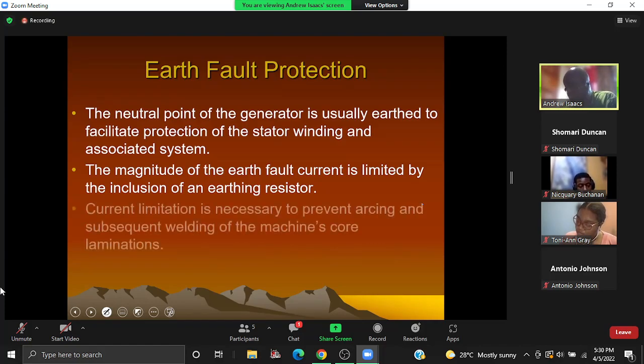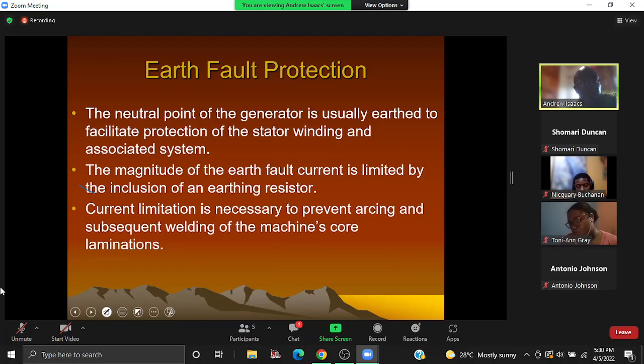So that's what we are referring to here, all right? And we are limiting the current because, one, we know that the generator is the unit or the equipment that produces all the fault current within the system. And I say that advisedly because your synchronous motor can do the same. But in the case of the fault on a machine, we are seeking to limit the amount of current that passes through it, right? To reduce, if not eliminate, the possibility of damage to the core.